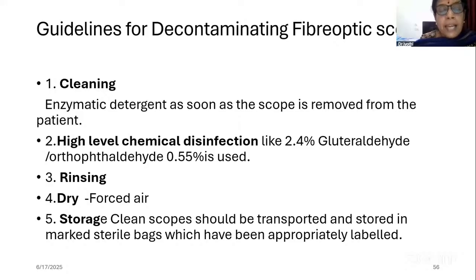This organic matter will be the cause for persistence of microorganisms in this scope. So cleaning with enzymatic detergent is very, very important to remove all the organic matter from the scope. Then high-level chemical disinfection, like 2% glutaraldehyde or orthophthalaldehyde, can be used. Then cleaning, high-level disinfection. After that, rinsing with sterile water, then dry.